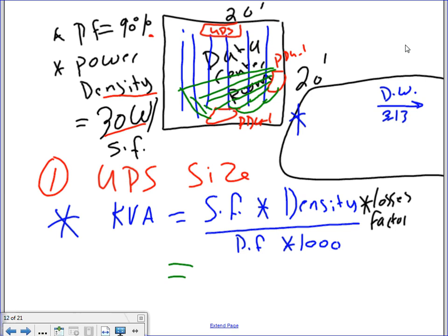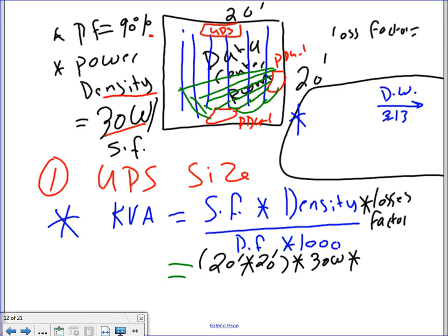Okay, what's the square foot of this building? I'm telling you guys, the square foot of this building is 20 feet by 20 feet. That's the square foot of the building, multiplied by the density of this data center, which is 30 watts, multiplied by the loss factor. Can you guys put loss factor equal 10%? I have a loss factor of 10% I need to accommodate for.